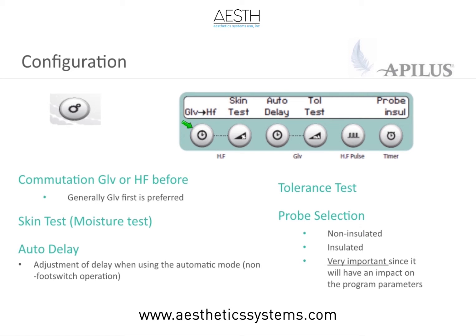So the configuration menu will display the galvanic lead. When we do blend, you can lead with high frequency or galvanic. This will only be visible if you were previously in a galvanic or blend mode. So I will show you where that's at, and that's the reason why my screen wasn't showing it just a second ago. The skin test is the moisture test that I said was only going to be available on certain units. And so my unit is a US unit, therefore we do not have it. I'll explain a little bit what that does, so if you have it, you can understand.